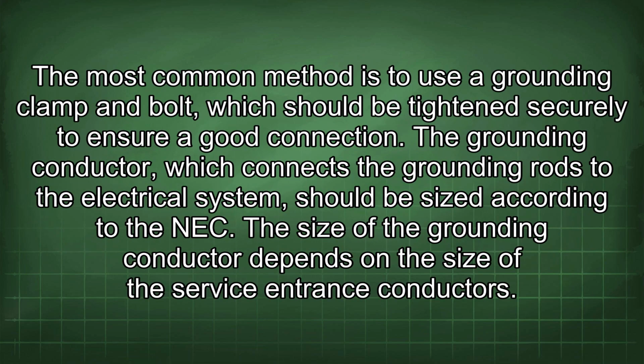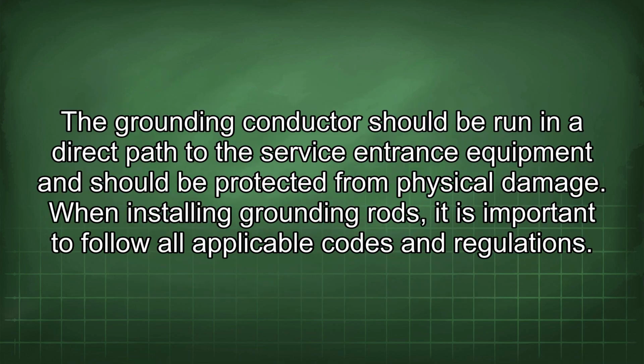When connecting grounding rods, it is important to use a method that creates a low resistance connection. The most common method is to use a grounding clamp and bolt, which should be tightened securely to ensure a good connection. The grounding conductor, which connects the grounding rods to the electrical system, should be sized according to the NEC. The size of the grounding conductor depends on the size of the service entrance conductors. The grounding conductor should be run in a direct path to the service entrance equipment and should be protected from physical damage.